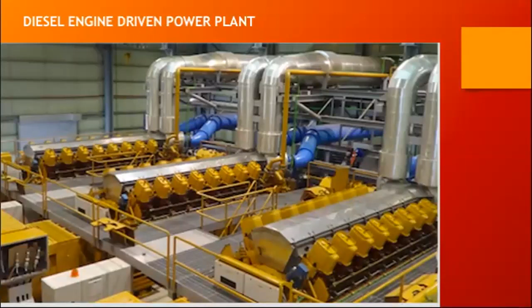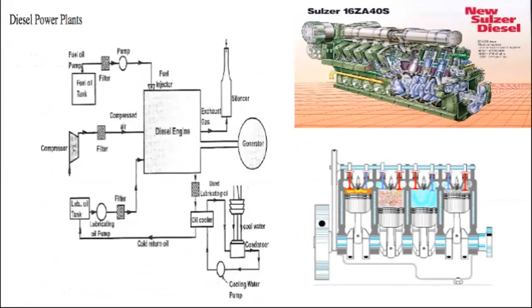This is a typical diesel power plant process. On the right side of the slide is a 16-cylinder V-type internal combustion engine. It drives an AC generator to generate electricity. To run reliably, a diesel engine needs a fuel system, compressed air system, lube oil system, cooling system, and exhaust gas system. The diesel power plant is capable of quick start and could be operated as a base load plant or as a peaking plant. A peaking plant is a power plant that generally runs only when there's a high demand for electricity for a short time.